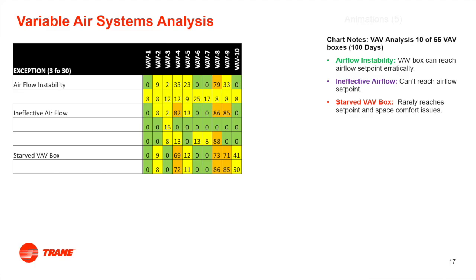Let's say we have this airflow instability algorithm written for one box, times 1,000 boxes, getting data every 15 minutes. It's impossible for us to figure that out manually. So what we do is look at that data over its life, over its time, and say this is our algorithm. Anytime we step outside of what we'd consider normal operation, we give it an exception—it gets a box check.